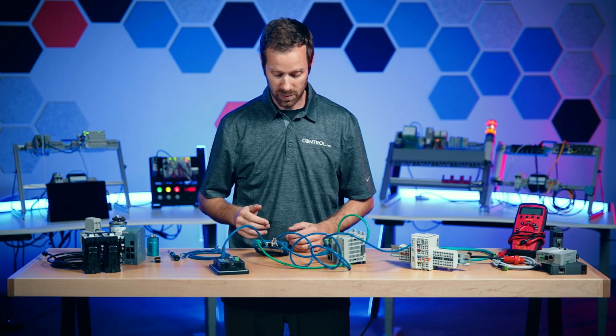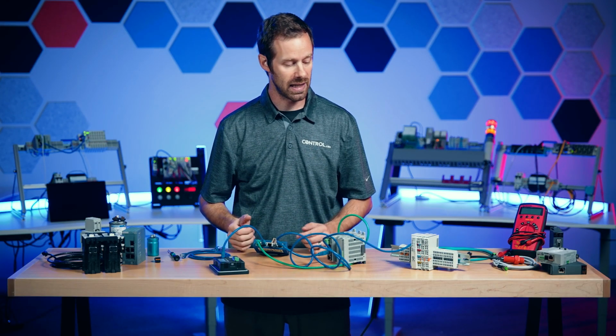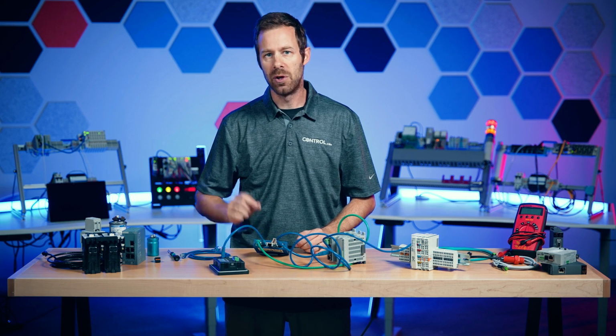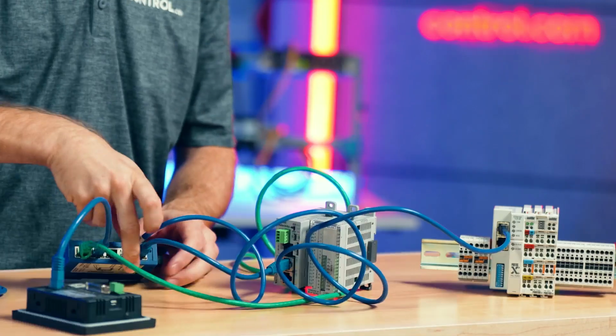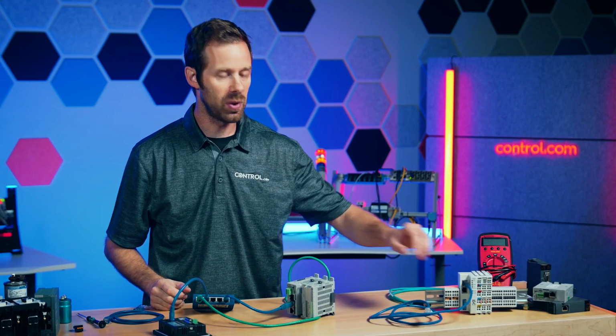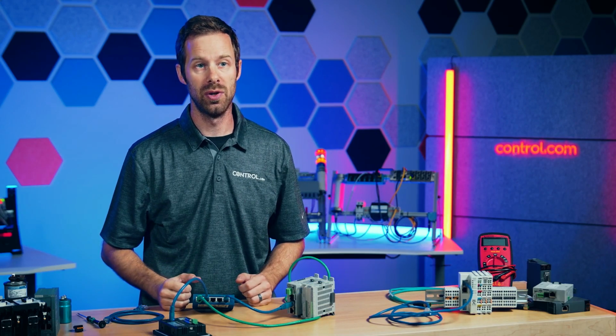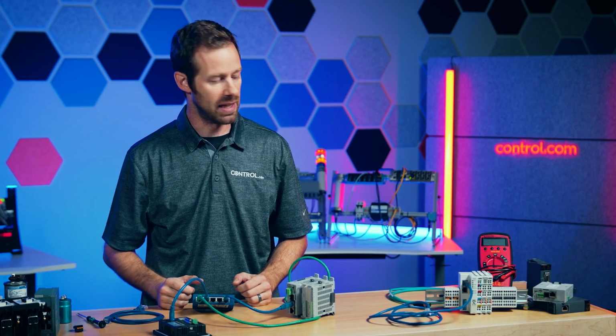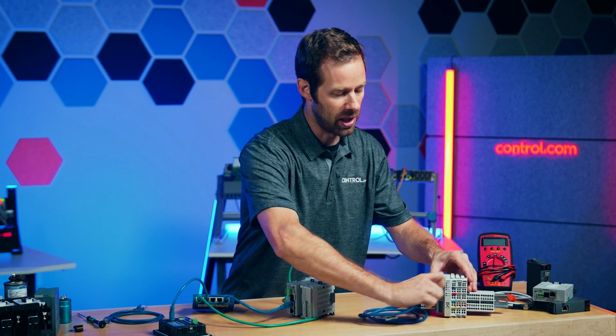If we think about a star, it's a central piece with a bunch of lines coming out of it. That's typically how we draw a star. This is a great system, lots of ports on our switch to be able to connect everything. But what happens if there's one failure in a cable somewhere? One wire comes loose, and all of a sudden we've lost a part of our critical control system. That's not great for redundancy. So let's look at another type of topology.